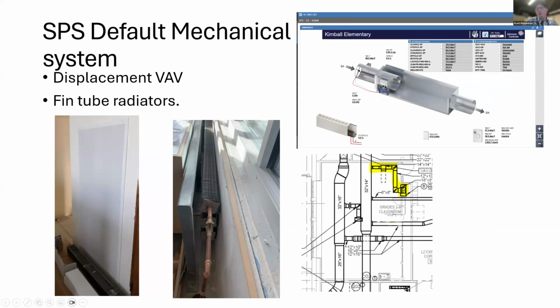Displacement ventilation, I added this picture here. I'm not sure if you guys have ever seen that, but it's just one huge diffuser. It has a very large footprint. So you pump a lot of air at a slow velocity, and it just kind of trickles into the room. You don't even notice it. It's very quiet, and the teachers love it. Here you can see one VAV box coming into one diffuser. A big problem with this, though, being on the floor and being so quiet, is you might find a bookshelf in front of it. And here are the fin tubes along the window.